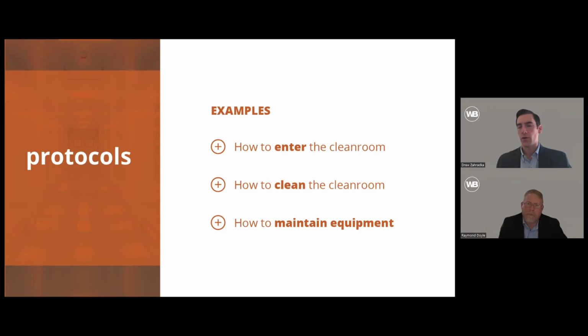And there are even protocols for maintaining the equipment. So this is inclusive of maintaining the lab equipment as well as maintaining the air handling units and the filters, and what are the protocols to change out the HEPA filters? Are the filters accessible within the space, or do we need to do a full shutdown of our air handling unit to maintain that equipment?